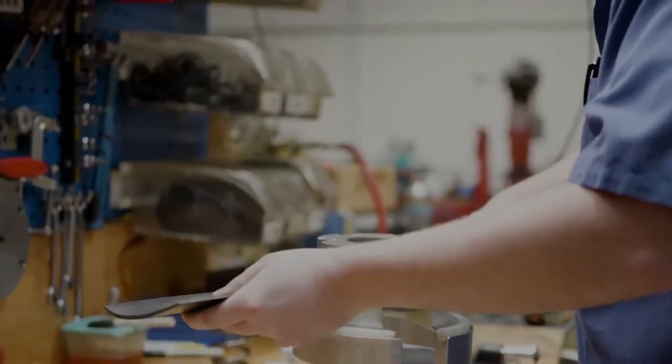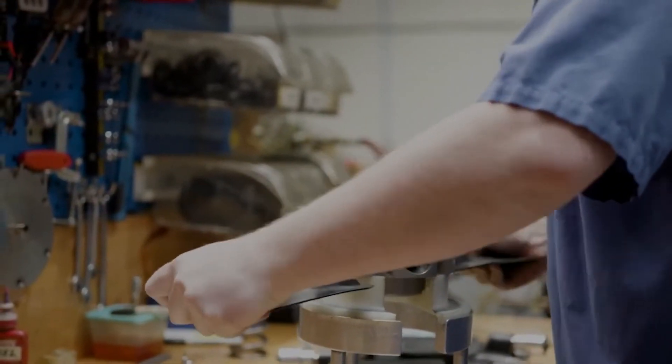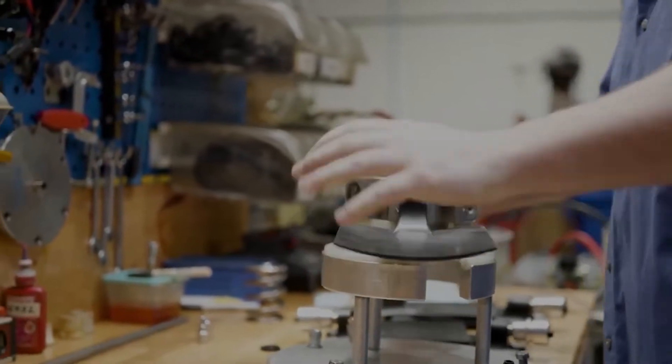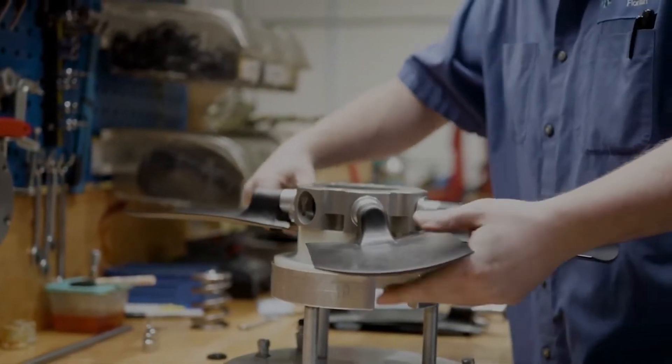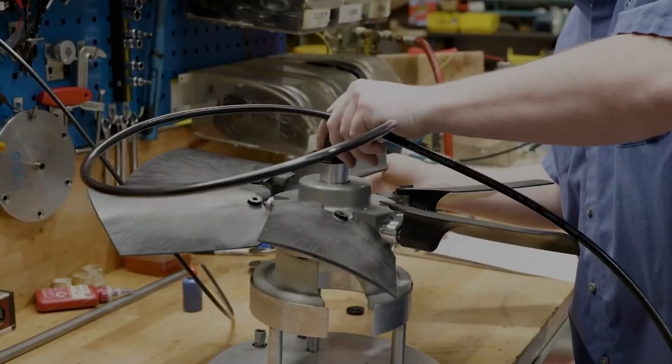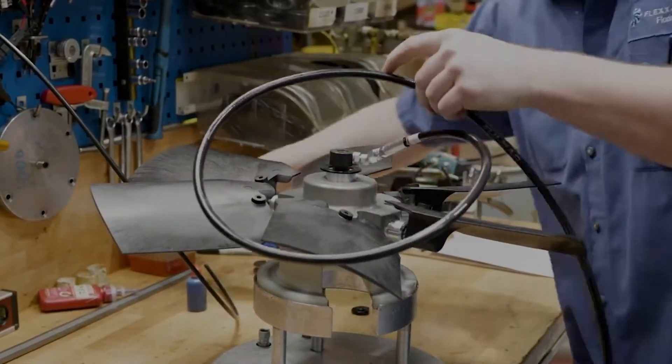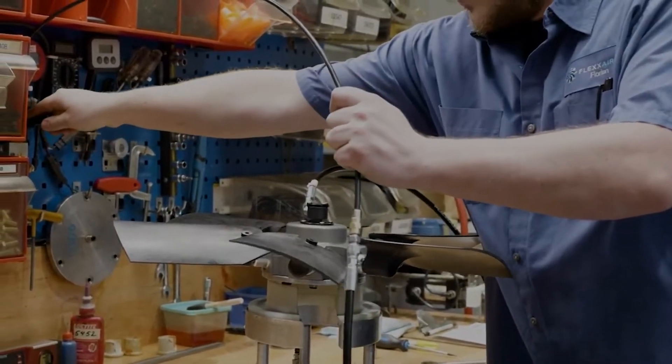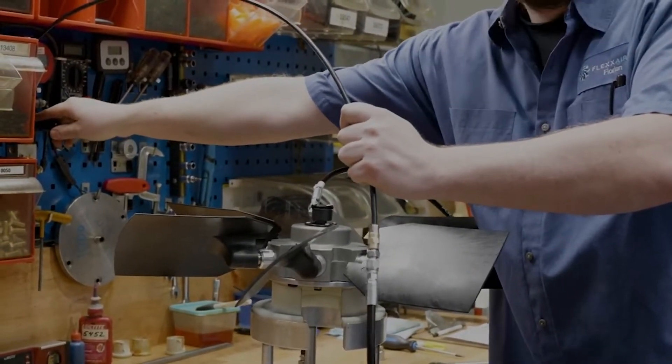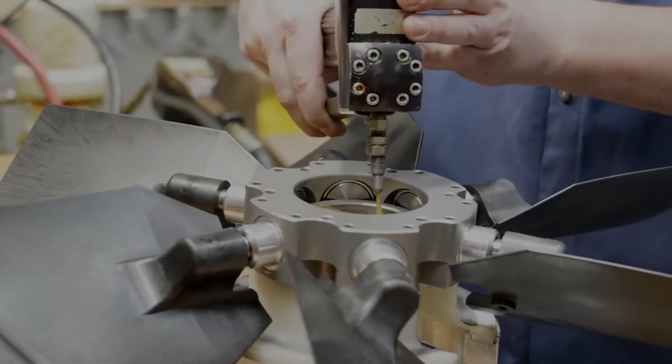Before our fans ship worldwide to our customers, they are assembled and tested. Prior to the final inspection and sign-off, each fan is subjected to a pressure and functionality test and is inspected to the drawing with pitch and diameter confirmation. This ensures each fan meets the required specification and functions correctly.